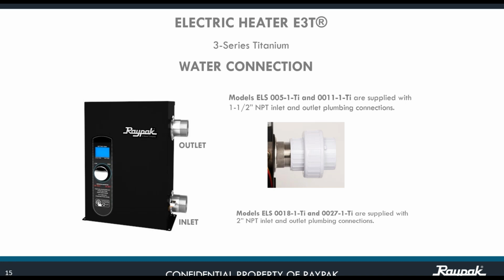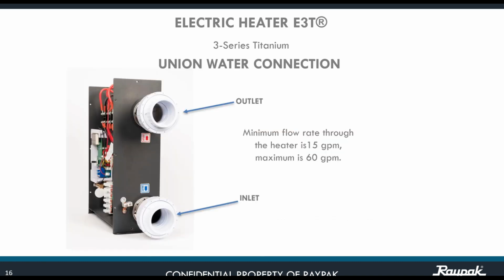In the other case, the 18 and the 27 kilowatts, we have a 2-inch NPT connection. That is going to give us a range of max 82 gallons per minute at 8 feet per second. Beyond those ranges, we're going to be in need of an external bypass. We're going to be seeing this in a moment. So just to have a completely clear picture, the minimum for all the units is 15 gallons per minute, and 60 gallons per minute is the max. If you are beyond that number of 60, then we recommend you use an external bypass.